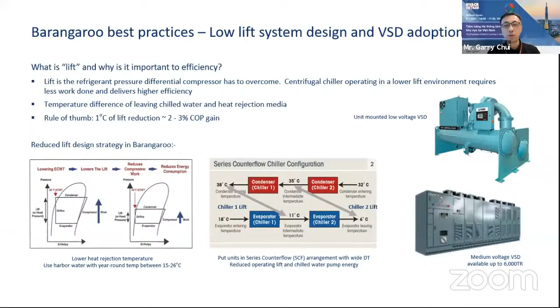Instead of using a freshwater cooling tower, and drawing in the Sydney Harbour water, the chillers are able to operate with a lower heat rejection temperature, with the seawater between 15 to 26 degrees C year round. That helps to lower the lift, which is the pressure difference for the compression. The other thing adopted in the design is what we call a series counterflow. Traditionally, maybe I will elaborate on that in the next slide. Next slide, please.